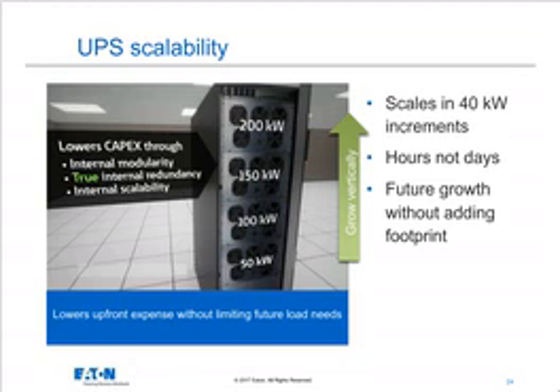But if my building grows or my application grows, then I might need to put in another 50 to make it a 100 kilowatt UPS, or a 150, or a 200 kW. Remember that if I add power capacity, I'm probably going to be adding battery strings as well. So allow the necessary floor space for this UPS to grow to its full capacity, even if that doesn't happen for multiple years down the road.